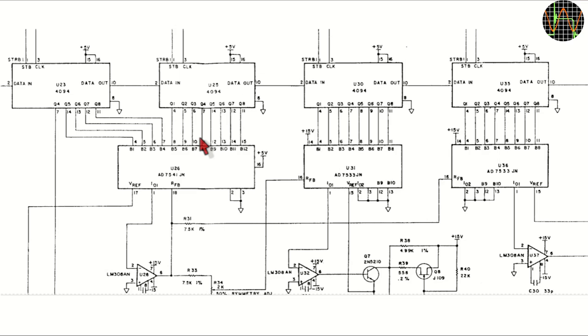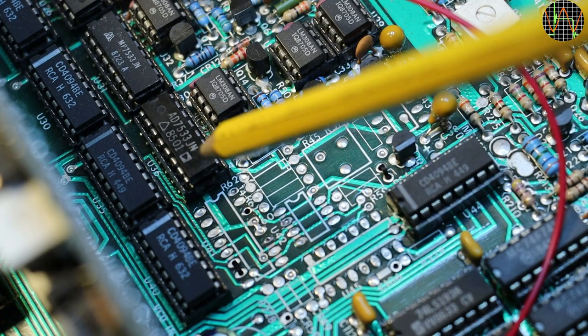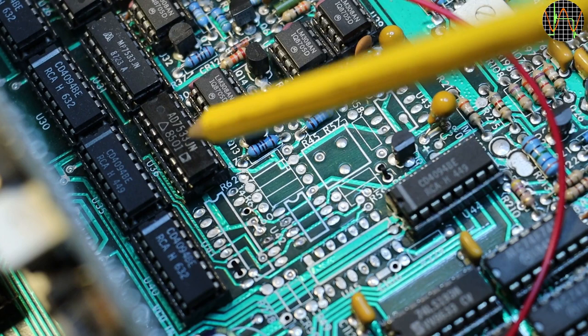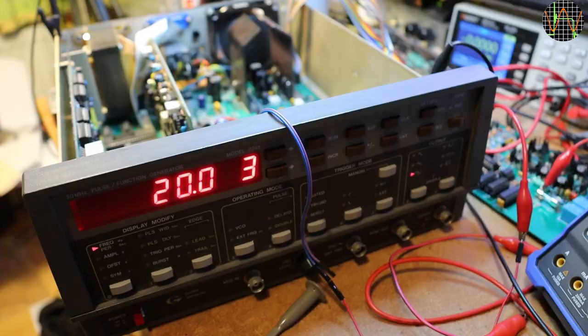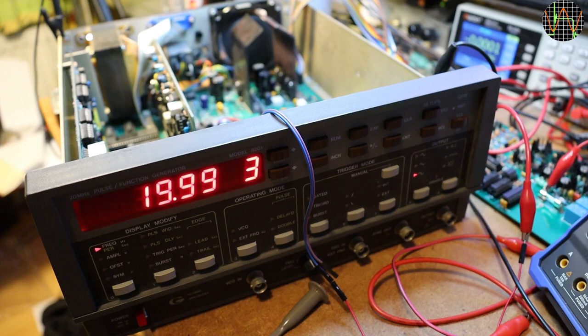Sure enough, I found that the signal at pin 1 of U36 did not change at all whatever was selected. I replaced it with the new AD7533 which you see here. This is the second of these chips that has gone bad. One wonders if there is a common cause, considering that this generator contains a lot more of these. Let's leave that for the future. As you can see, the new chip fixed the frequency error and frequency selection works fine now.